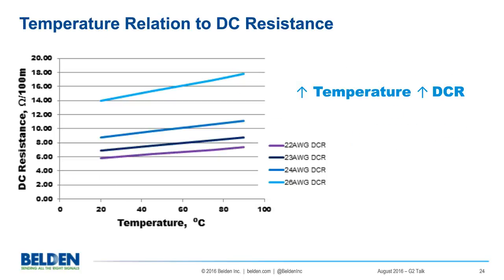Let's take a quick look at the temperature relation to DC resistance. The resistance of the cabling, as temperature goes up, in this case from 20 degrees Celsius, which is room temperature, up to 60 degrees Celsius, which is normal jacketing rated temperature, but there are some cables with jacket ratings of 75 and 90, and I showed those as well. And you can see that, again, the larger diameter wire, 22 gauge, is the bottom one. The resistance, per 100 meters, can go up roughly 1 ohm, which isn't a lot. But if we look at something smaller, like 26 gauge wire, which is the one on the top, we can see a dramatic increase of almost 2 ohms, and this is at 60 degrees C. And that's related to efficiency as well.